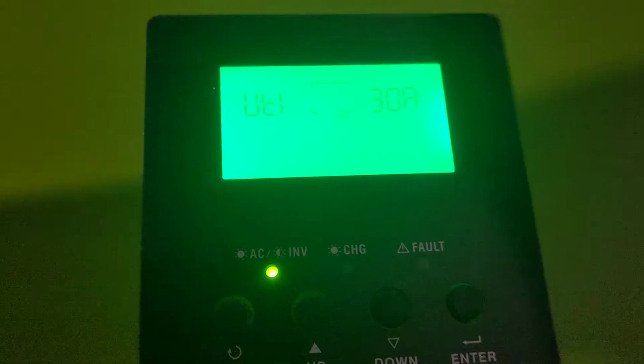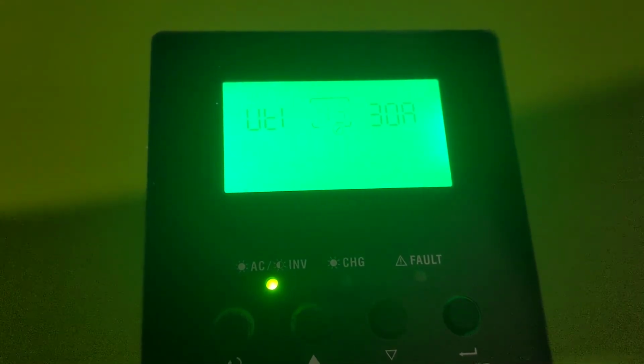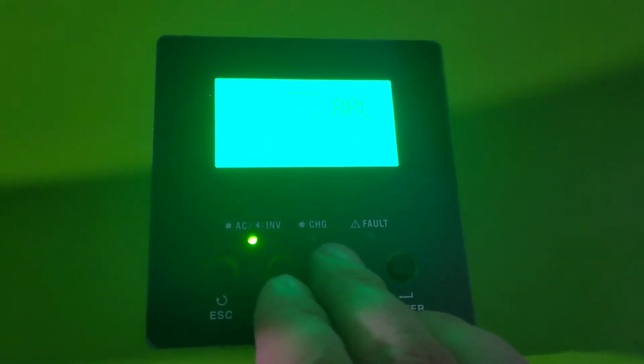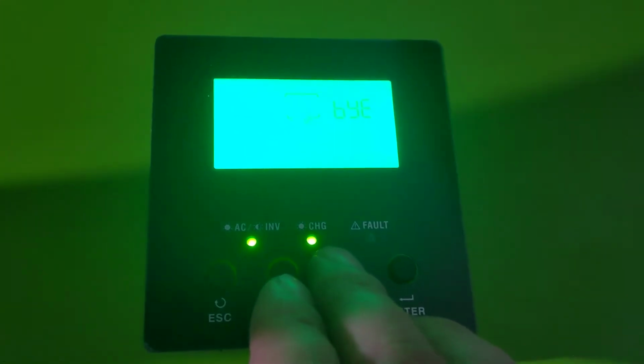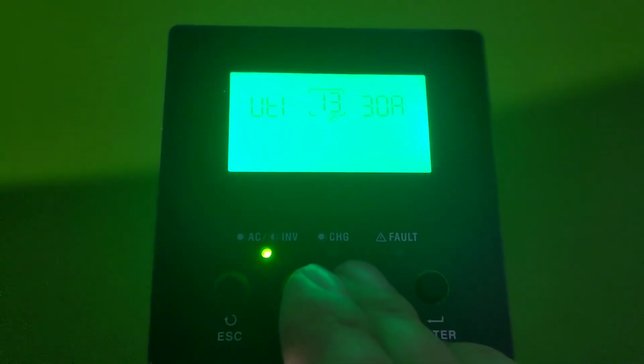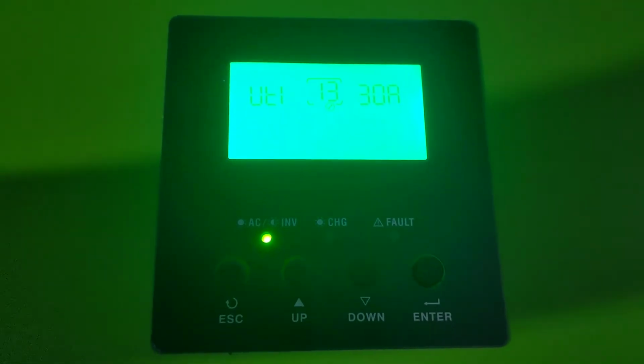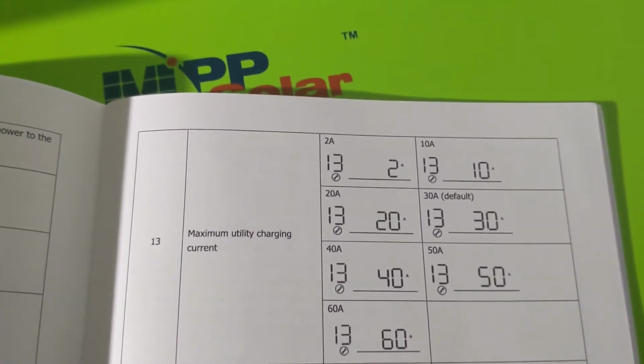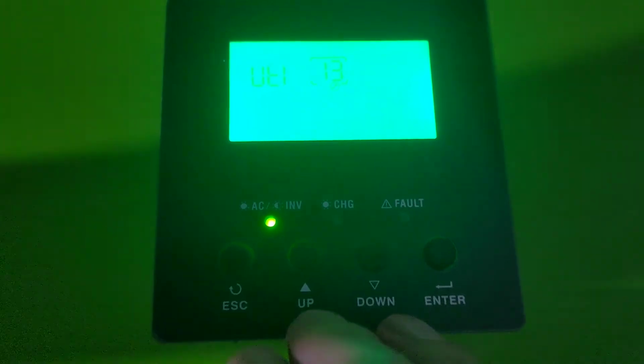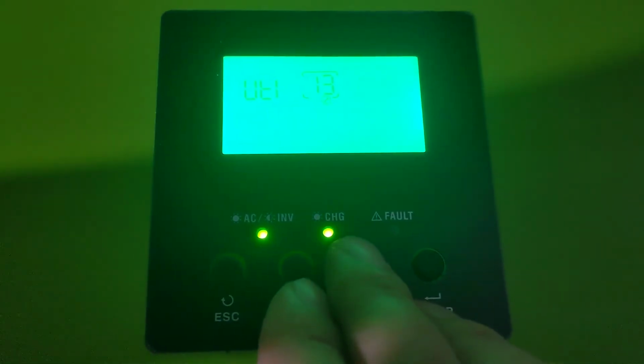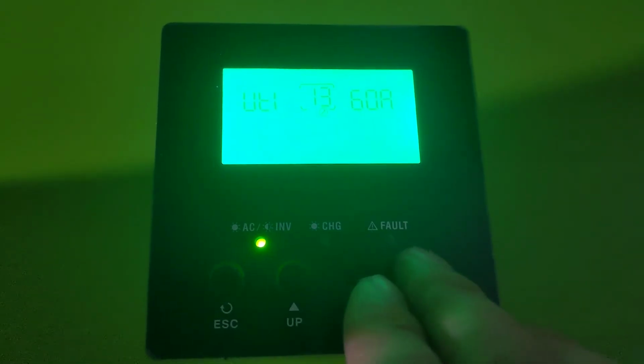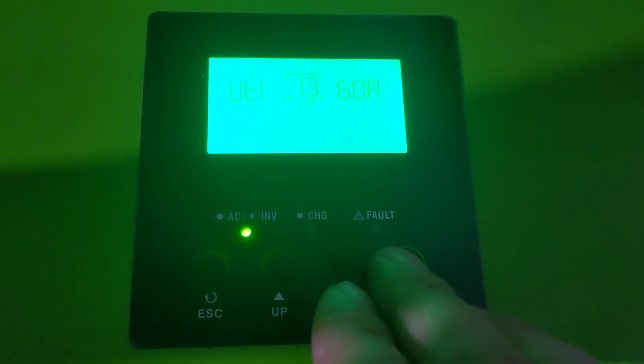Well, we found our first configurable that needs to be changed. 28 amps is what we were getting. The way to change that is to find your maximum utility charging current setting. This device is capable of 60 amps. So, there it is. We go to item 13, as we see here, and I'm going to select this, change it, don't want down, change it to 60 amps, enter. Okay.